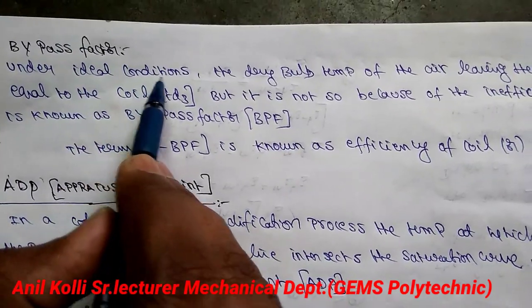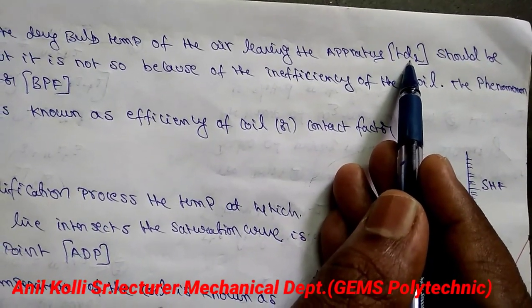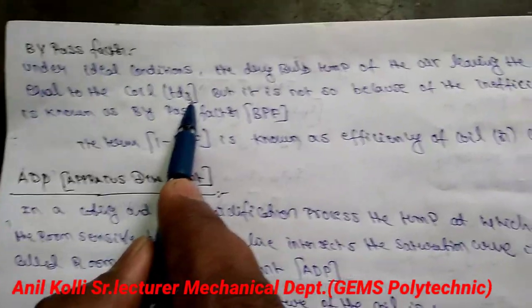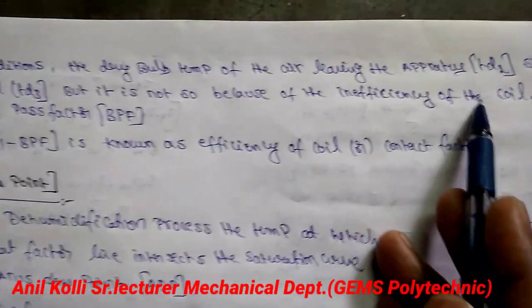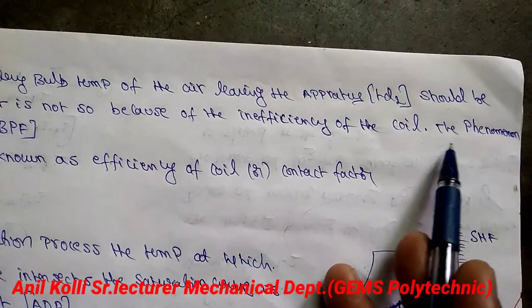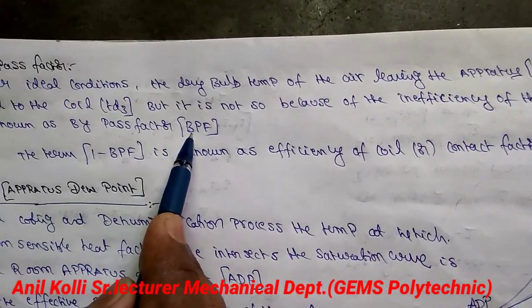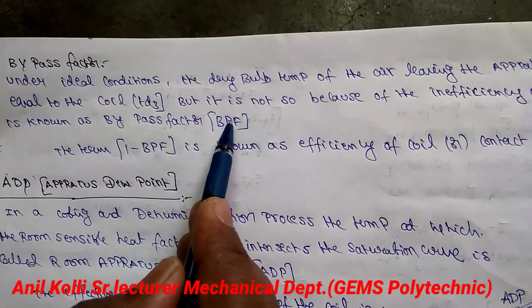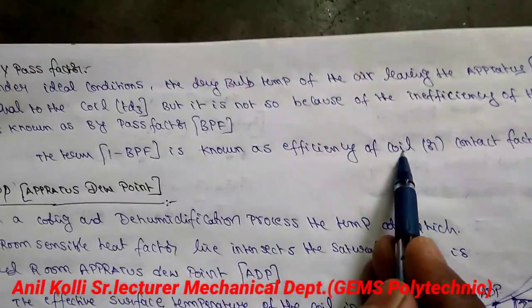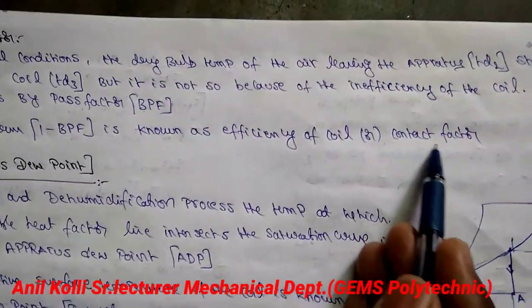First one is bypass factor. Under ideal conditions, the dry bulb temperature of air leaving the apparatus (T2) should be equal to the coil temperature (T3), but it is not so because of the inefficiency of the coil. This phenomenon is known as bypass factor, briefly written as BPF. The term 1 minus BPF is known as the efficiency of the coil.